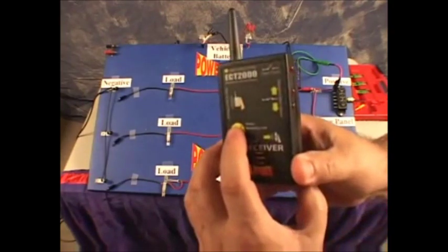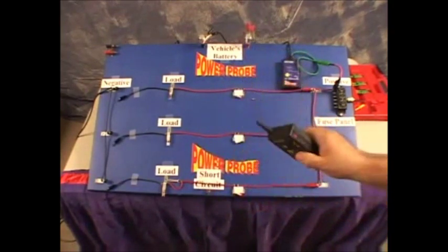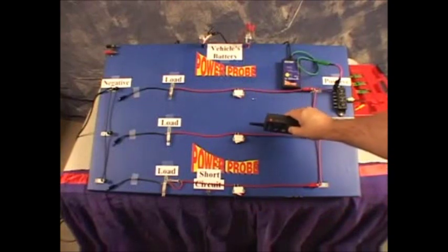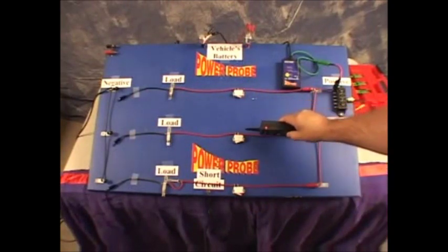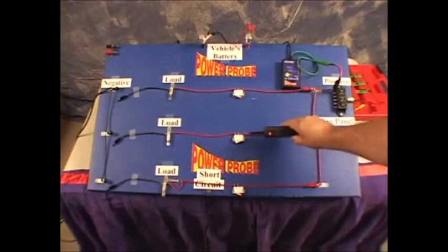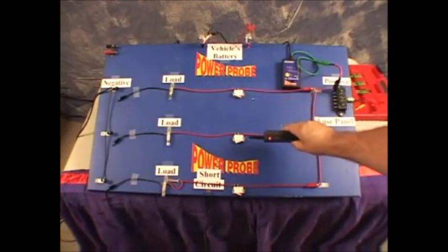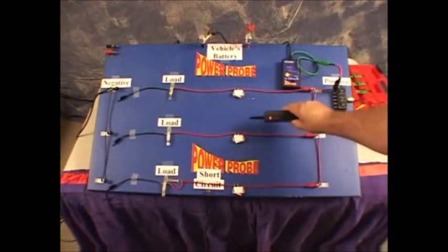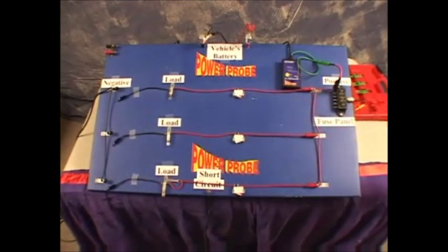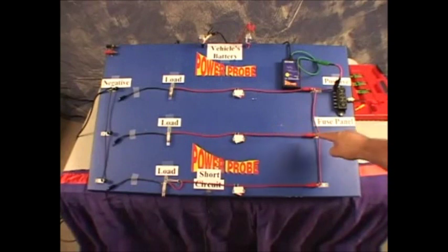Let's turn on the receiver and hold it over our problem circuit about 3 inches away and lock the reception sensitivity. As you can see, the problem here is that we're receiving signals from all 3 branches. Remember the main rule: you have to isolate the circuit you want to trace away from the other branches.